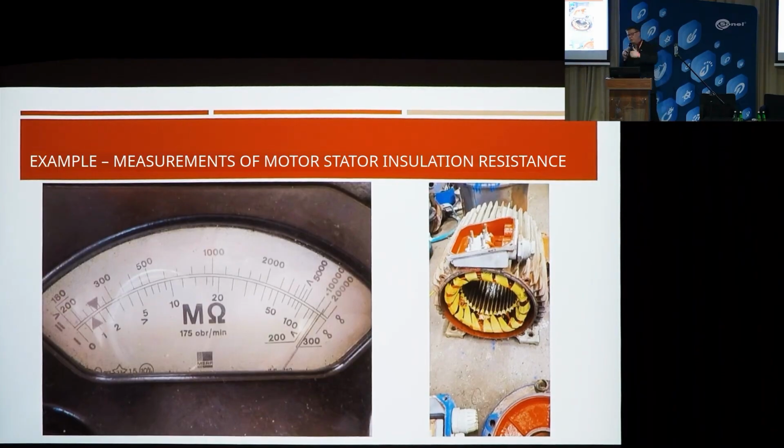It's after rewinding, already taken out of the oven, varnished, all done. Basically perfect, supposedly perfect. And here you can see on the meter, on that hand-cranked IMU meter, that the needle, maybe you can't see it exactly here, that's true, but it's already hit the stop pin. So that was the maximum.